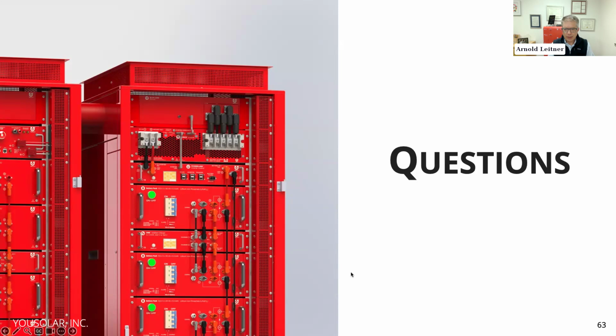Can you do a 200 ampere configuration with a 70 kilowatt hour storage system? That question came up. The answer is no, but it's a soft no, not a firm one. We need 30 kilowatt hours behind the inverter on the boost battery to deliver 600 volts. Power and energy storage are tied through a discharge factor.